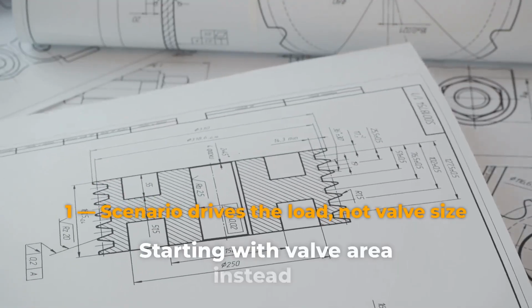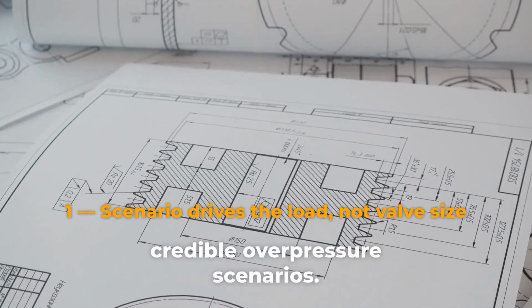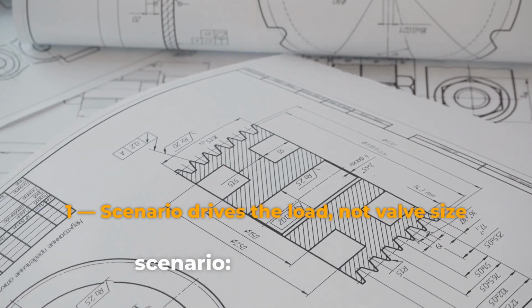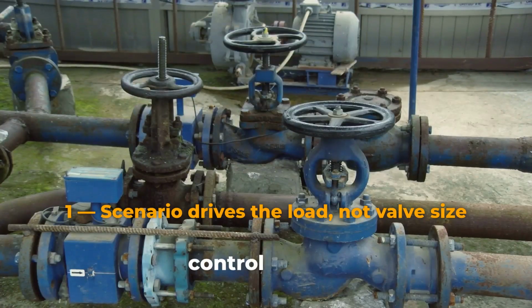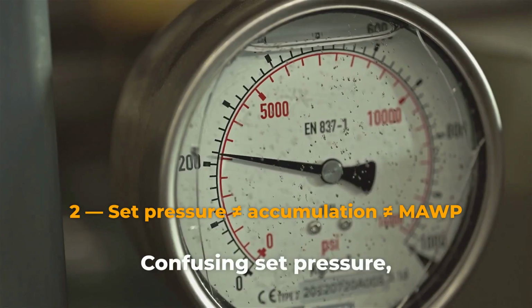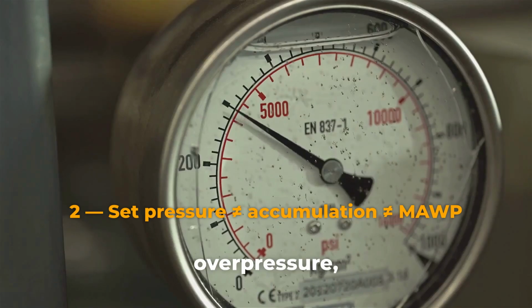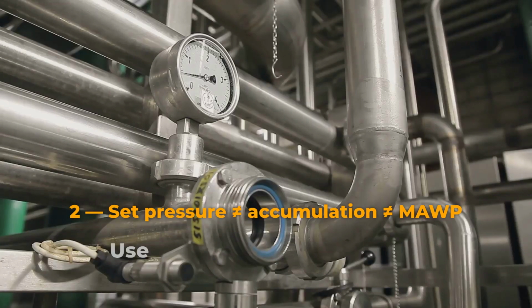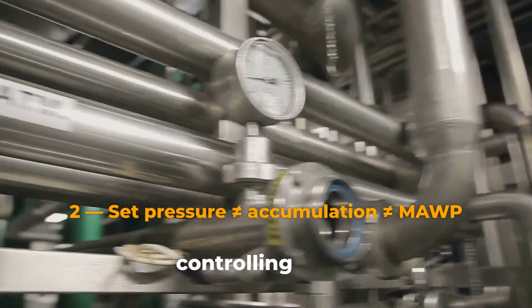Mistake one: starting with valve area instead of credible overpressure scenarios. The required load comes from the scenario: blocked outlet, control failure, fire, thermal expansion, tube rupture, or gas blowback. Mistake two: confusing set pressure, accumulation, overpressure, and MAWP. Use the definitions and limits in the controlling code.